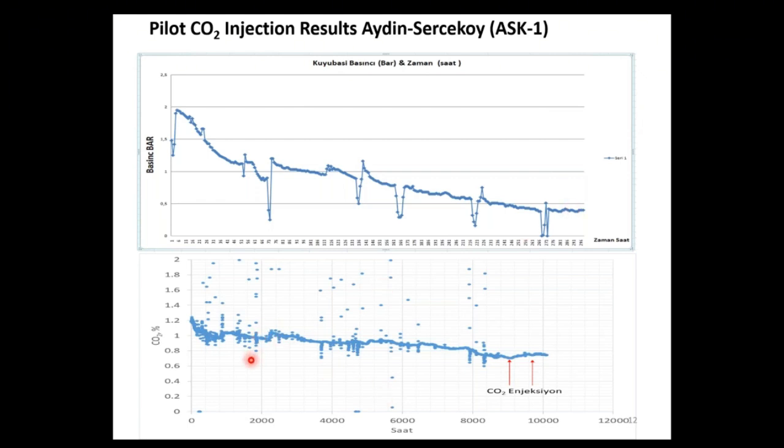The second one is, when you measure your CO2 rate, or let's say concentration, at your condenser, this is the first initial value of the ASK-1 well. As you see, this is, I think, one of the production wells. It's not written here. It is the ASK-1 injection, the NCG injection. This is the power plant which the ASK-1 production wells are connected to. Their average NCG, as you see, is 1.2 per weight rate. I mean concentration.